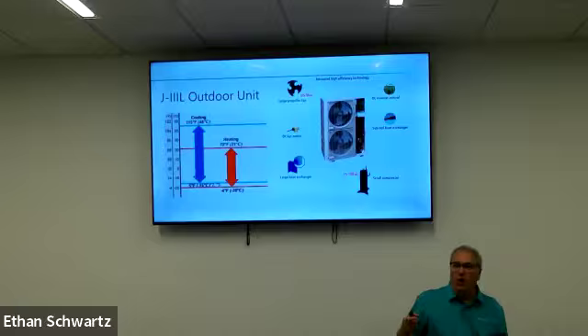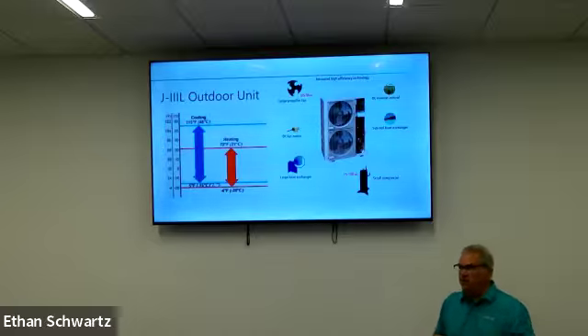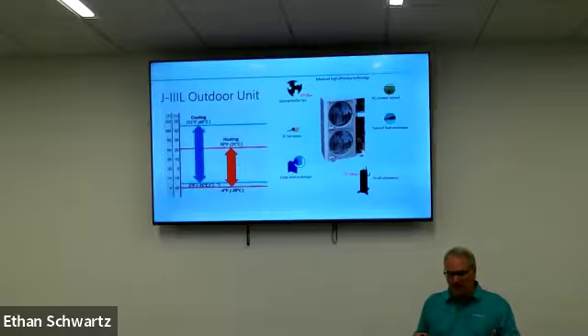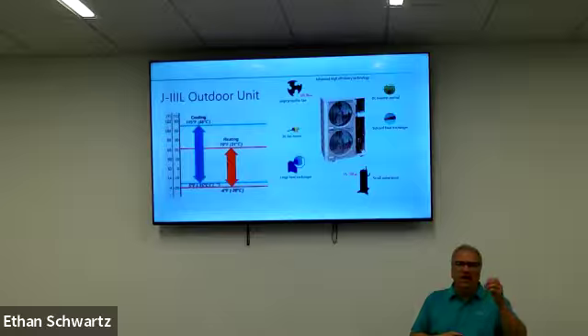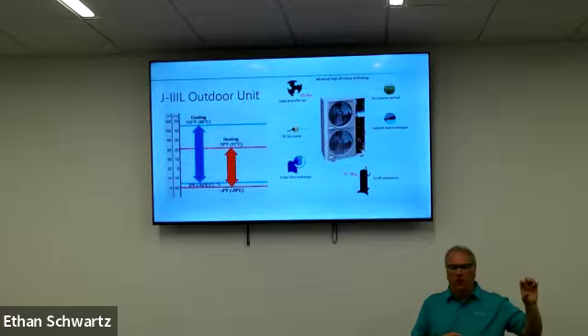So where does that leave us with the R32? Again, I don't do a lot with the H series, but these are the things I get into on the engineering side application. The 18, 24, 30 and 36 AOUH KPAS1, if I got the number right, those are all low ambient cool. And I was asked, and it's kind of died off now, when I first started with Fujitsu: why don't they make a 9,000 BTU low ambient cooling wall mount or cassette? Why don't we do that? Because the cooling load is so small.